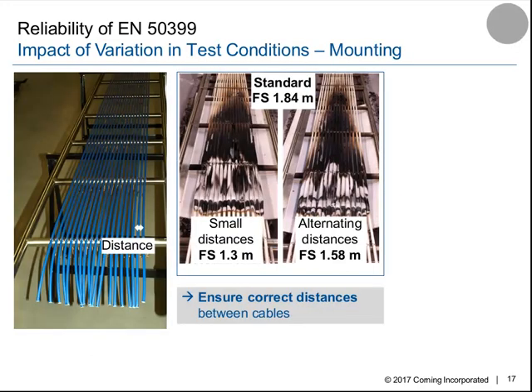So let's start with the mounting procedure. Mounting in the standard is defined in regard to the distance between the cables: one cable outer diameter of distance needs to be between the cables, and the overall width should be 300 millimeters. We were wondering what happens if the distances are a little bit smaller, somewhat like 8 instead of 10 millimeters for our calibration cable. Yes, the overall width would be reduced, so you could measure that it's smaller. But if you just have a look at the ladder, as you see it here, you cannot identify that it's really a smaller width.